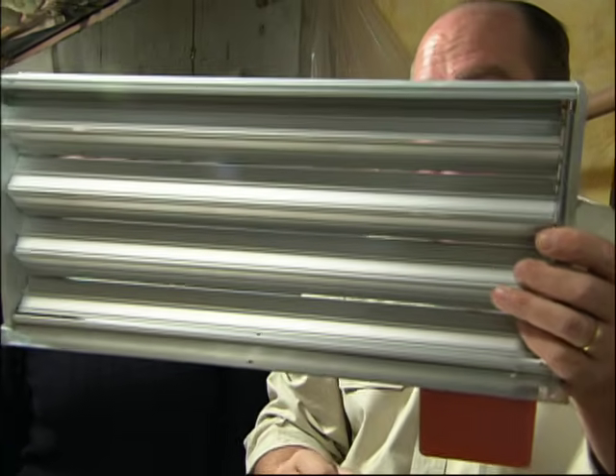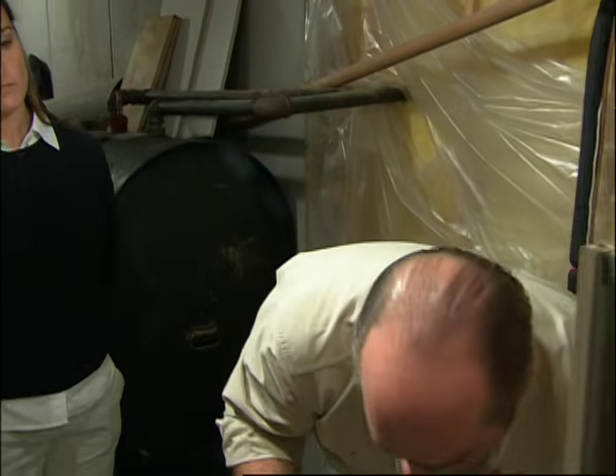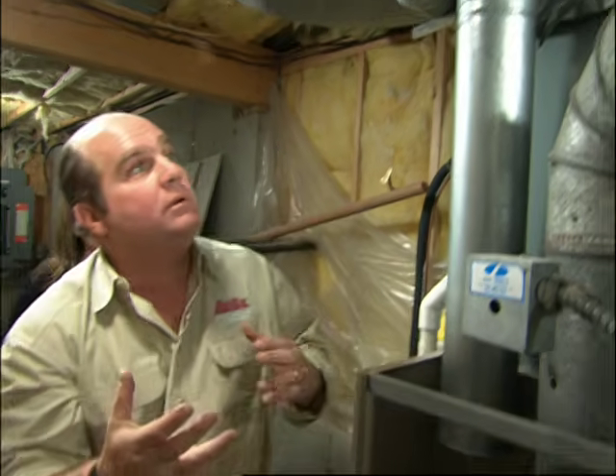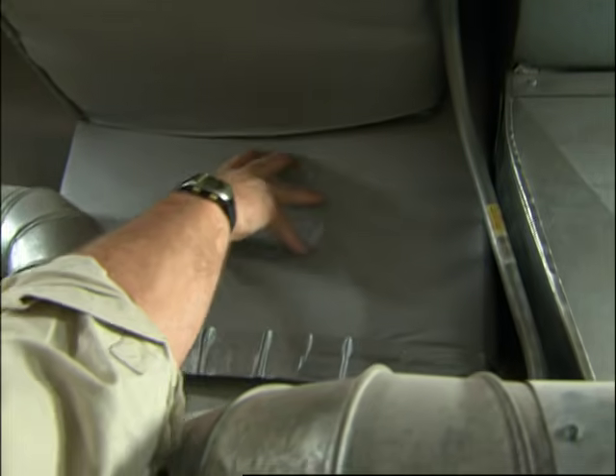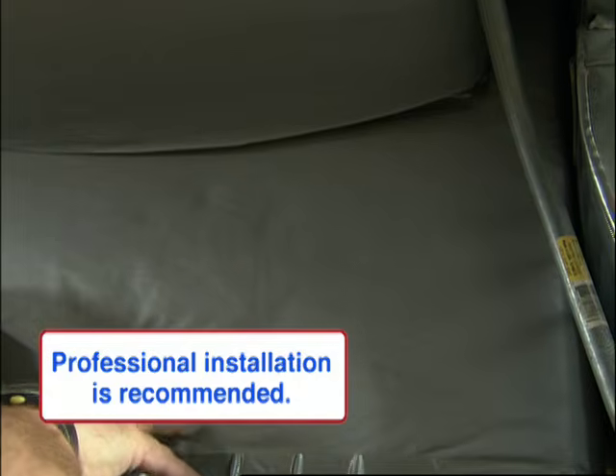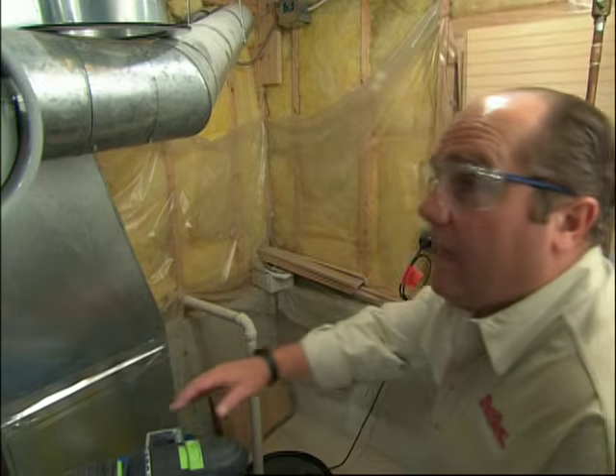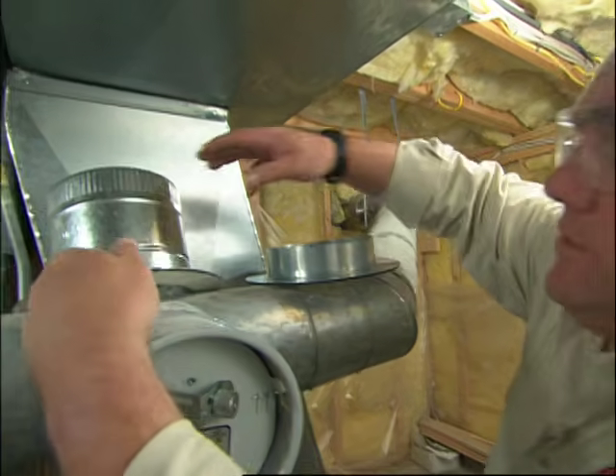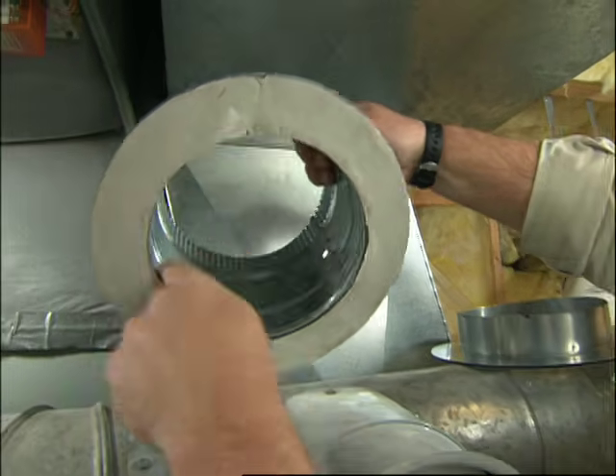Okay, so what do you think we can do to correct this? Well, because it is a buildup in pressure, we actually need to put in the equivalent of a relief valve. In this case, it's called a bypass damper. We need to cut in off the supply right here and relieve the pressure that's building up inside the plenum. Now to tie into the ductwork, we're going to use these start collars. Now these are 7-inch round.